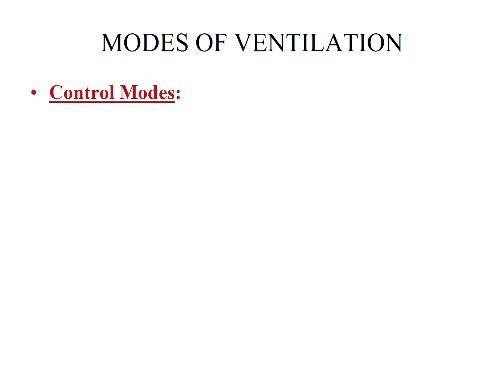Generally speaking, the control modes are the ones where each breath is fully supported by the machine. So the breath is initiated by the machine. One, the initiation or trigger is done by the machine. Two, it is limited by the machine, meaning how much air and over how much duration air is going to be given is controlled by the machine. So triggered by the machine, limited by the machine. And when does this respiratory cycle finish and a new cycle start? Cycling, the third thing, is also controlled by the machine. Trigger, limit and cycling are controlled by the machine in control modes.